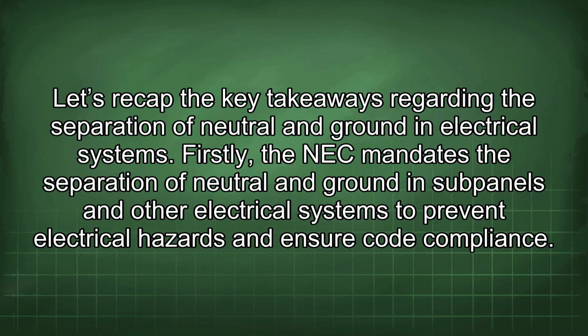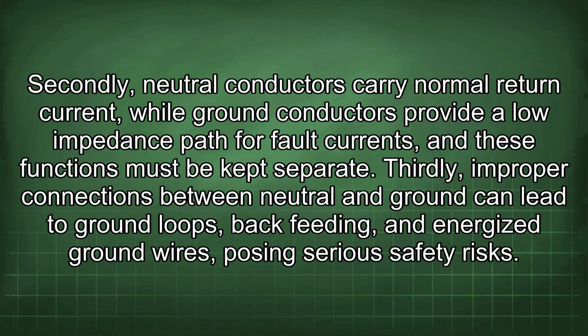Firstly, the NEC mandates the separation of neutral and ground in subpanels and other electrical systems to prevent electrical hazards and ensure code compliance. Secondly, neutral conductors carry normal return current, while ground conductors provide a low impedance path for fault currents, and these functions must be kept separate.